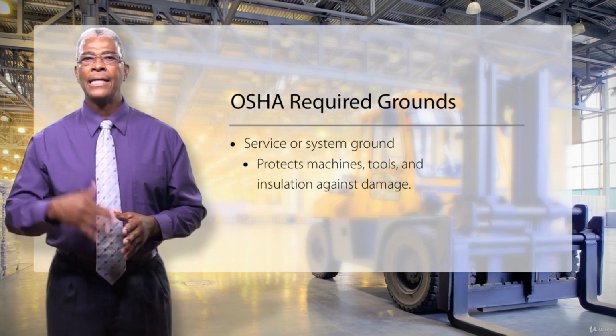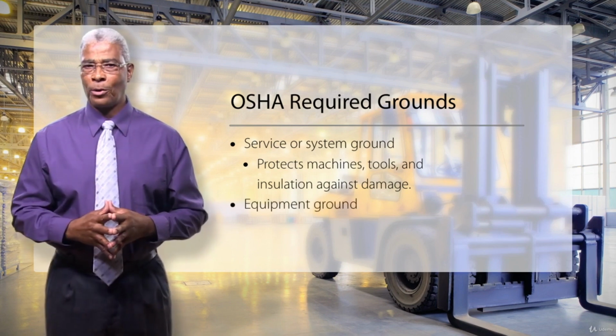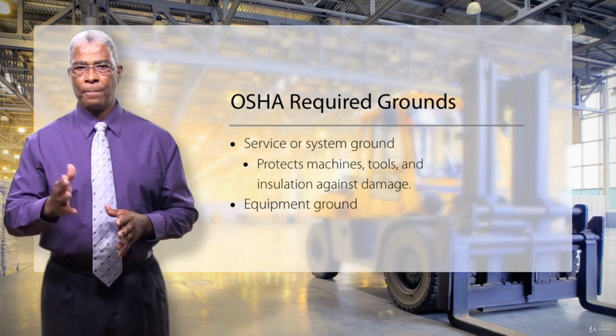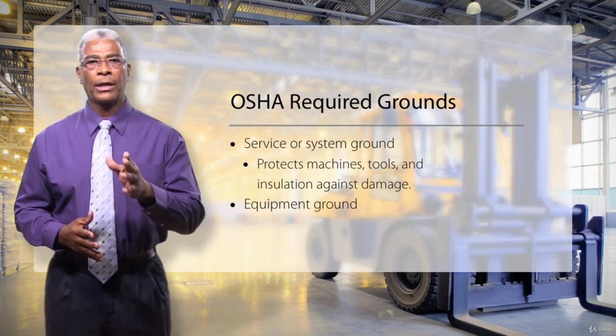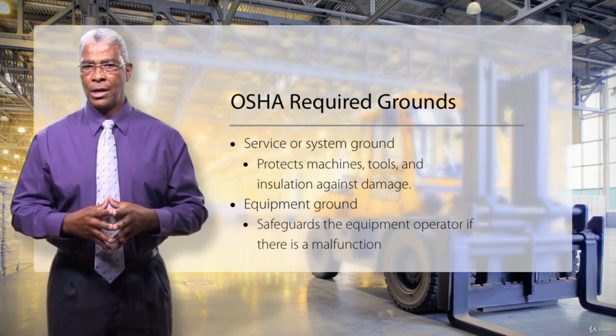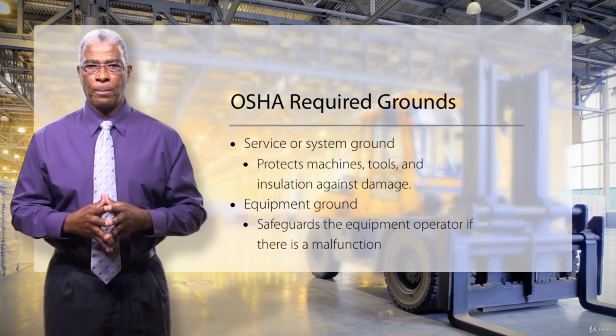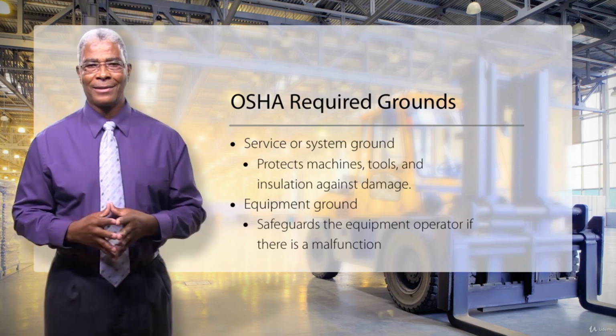The other type of ground is the equipment ground. This enhances worker protection and must be furnished by providing another path from the tool or machine through which current can flow to the ground. This safeguards the equipment operator if a malfunction causes metal parts of the equipment to become energized.